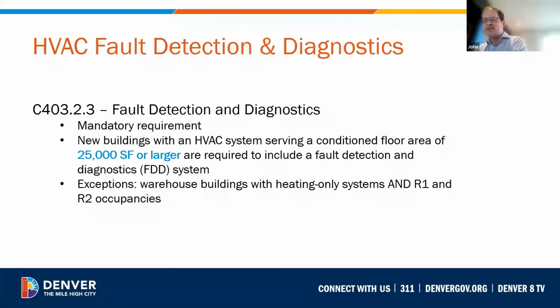For smaller, medium-sized buildings where there may not be dedicated maintenance staff on hand for each building, it's especially useful to have these systems in place that can detect faults before they become either chronic energy increasing faults or faults that actually impact the operation of the system and detract from the expected life of the system.